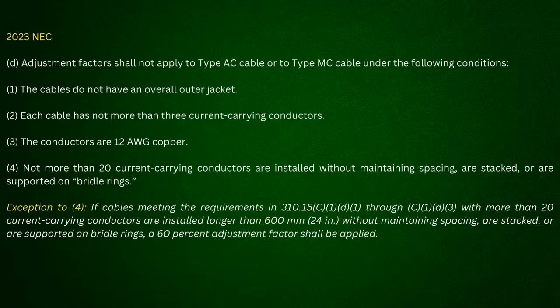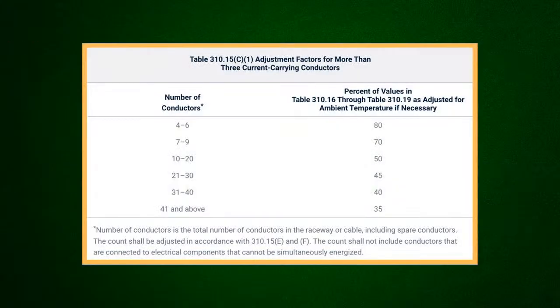These are a bunch of cables that are tied together, and they're basically putting some limits on it. And it says if you have more than 20 current carrying conductors that are installed longer than 24 inches without maintaining spacing or stacked or supported on bridle rings, a 60% adjustment factor shall be applied. There's your adjustment factor. That's how they tell you to do it. They literally give you rules to do it. But when it comes to a sleeve and everything, there's no rules for that. Yeah, now I agree. Especially with our little nipple experiment, because I pushed the limit. I tried to get as many number 12s as I possibly could in a 3/4. And I'm adamant that 26 is the limit. Yeah. Well, I can't get much more than that.